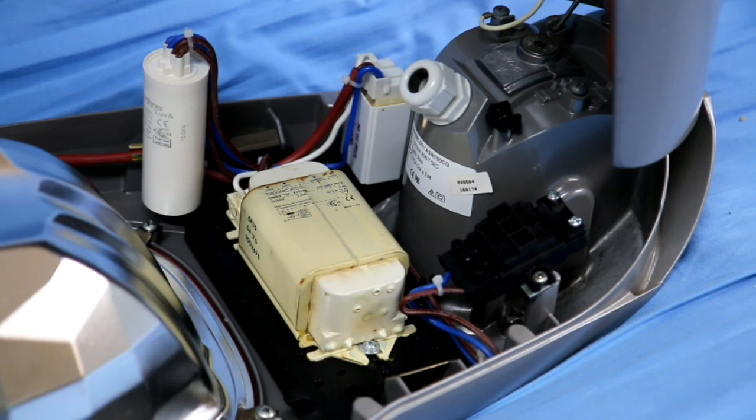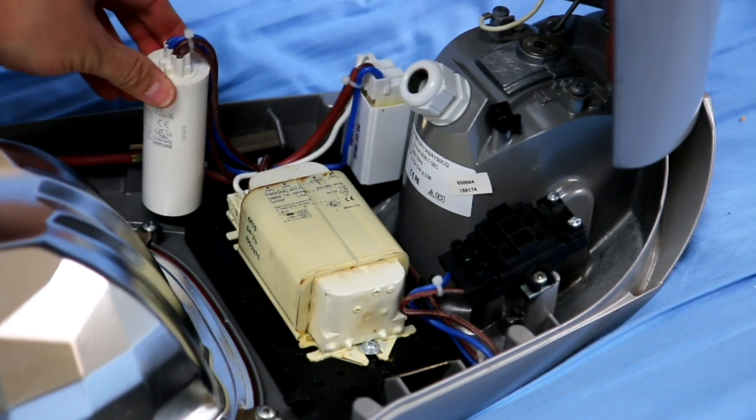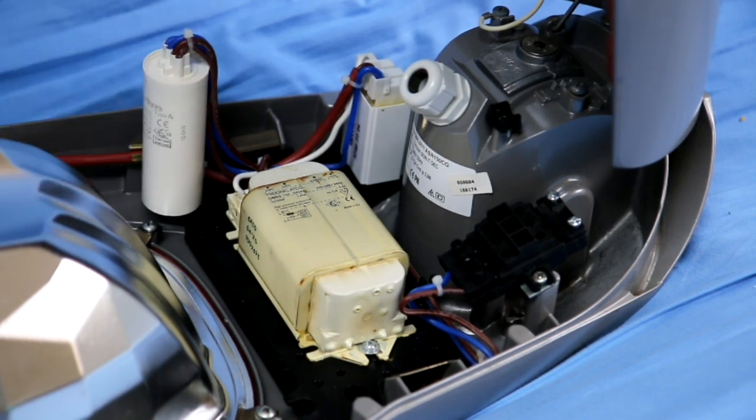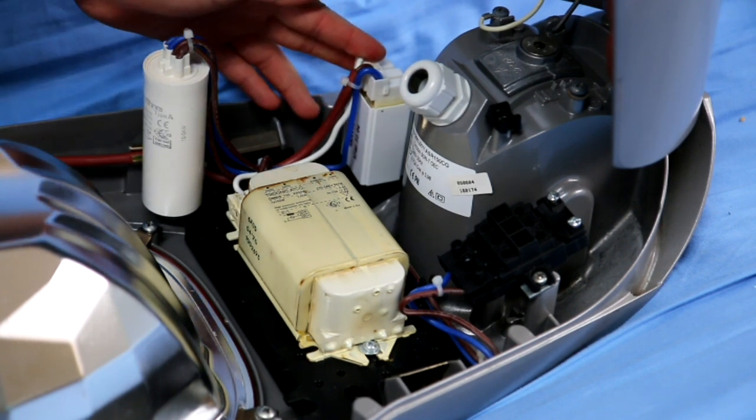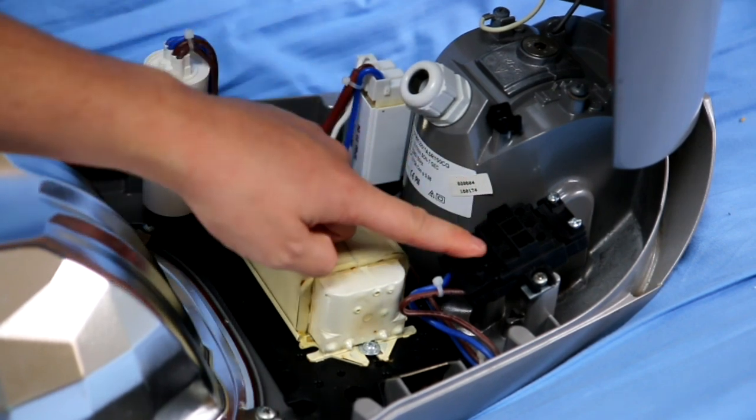And the capacitor on the left hand side here purely for power factor correction, it's rated at 20 microfarads. This is the superimposed igniter here and your terminal connection point.